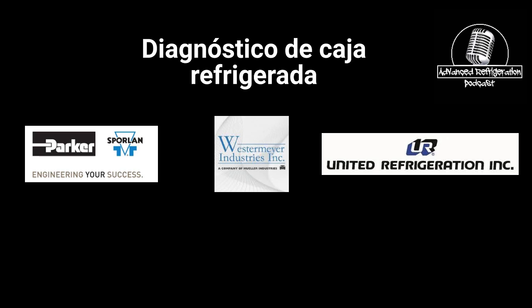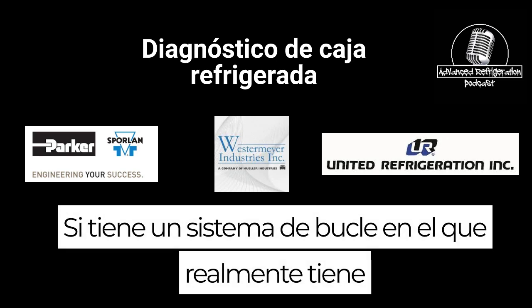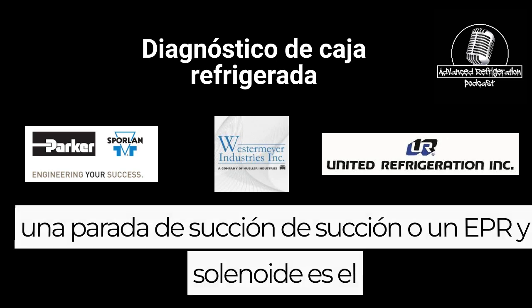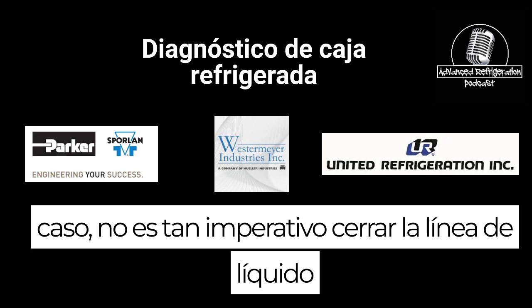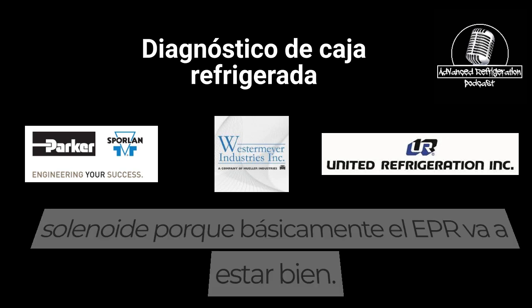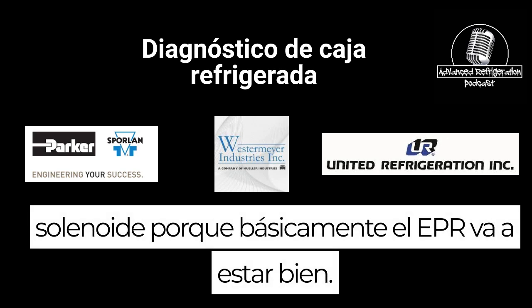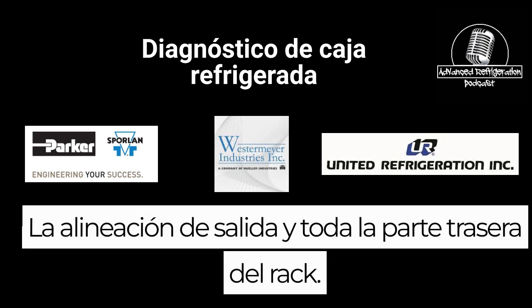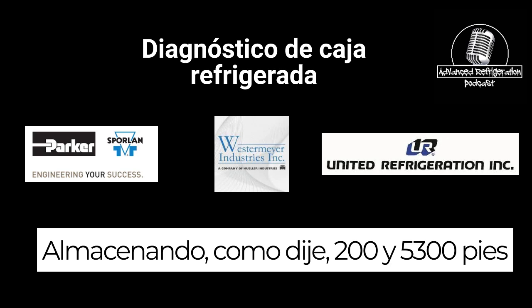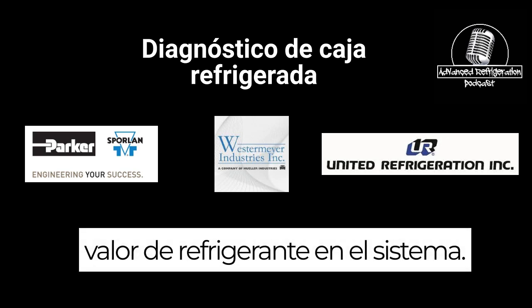If you do have a loop system where you actually have a suction stop, or an EPR and solenoid at the case, it's not as imperative to shut down the liquid line solenoid, because basically the EPR is going to be right at the exit, and not all the way back at the rack, storing, like I said, 250, 300 feet worth of refrigerant out into the system.